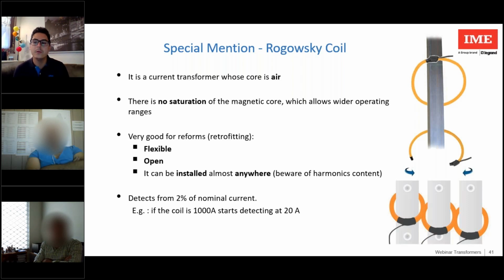So this is to tell you that for currents below 20 amps, it will be better to go for the classic current transformer. Rogowski coils are sold in kits with the NEMO 96 HD LE and D4 LE. For those who have missed it, they will find a link in the email post-webinar to go and review that course.